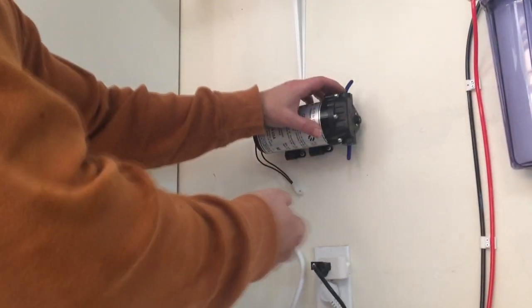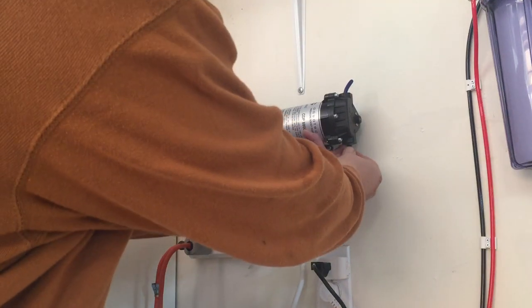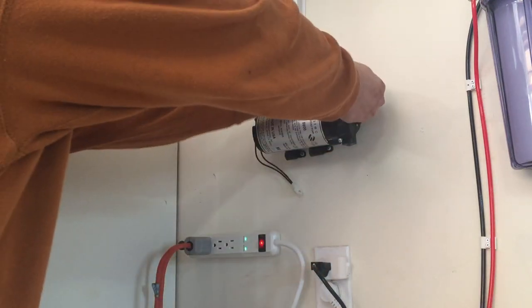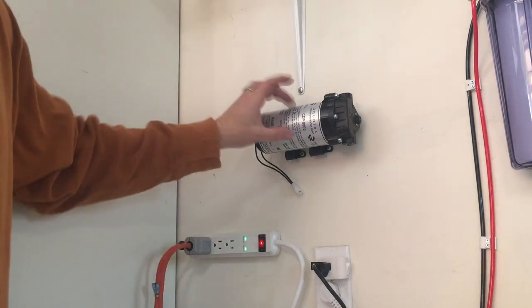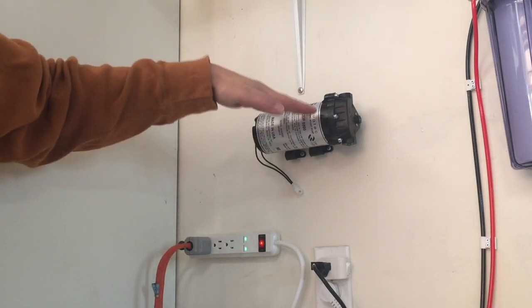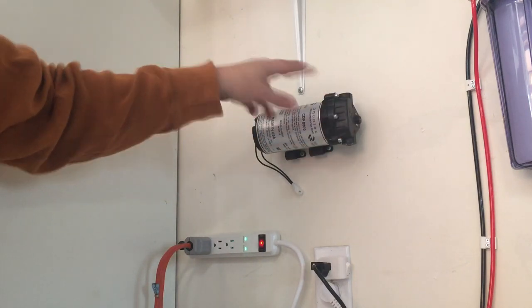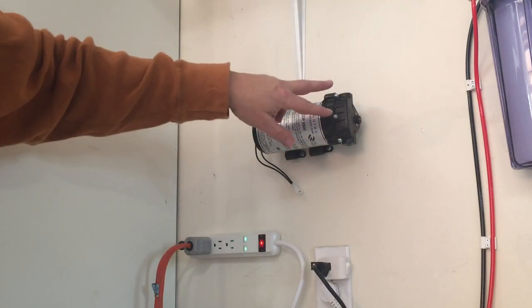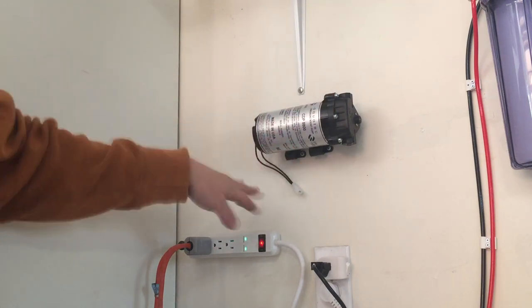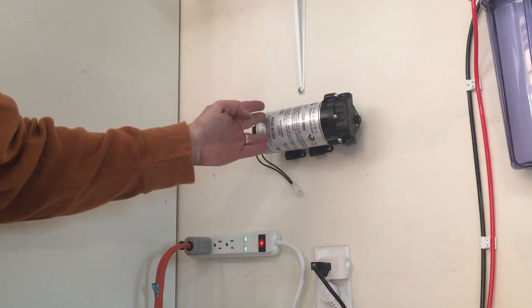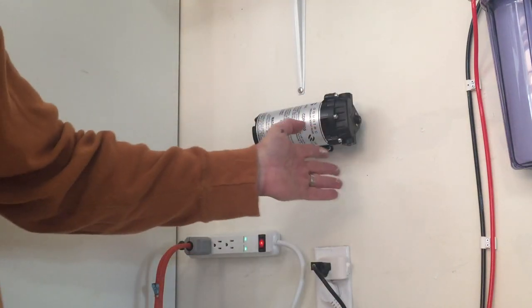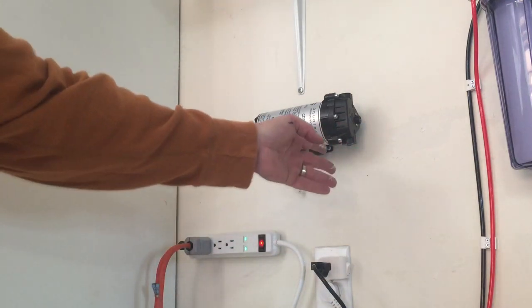I'm going to remove the rubber caps that are shipped with it. Just pull those out. That's where we'll connect the supply. Note that the recommendation is that you mount this either with the tubes on top, which is the preferred method, or on the side secondary, but on the bottom you might get air trapped in here, which may prevent flow later on. But because of the location to the electrical here, I want to keep it clear, so I'm going to mount it to the side.